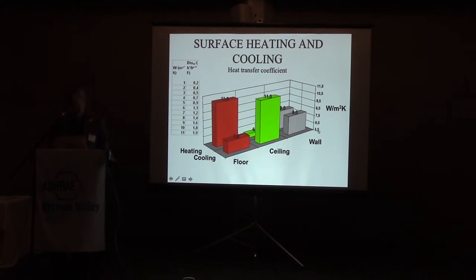So that's mainly radiation. If you have a ceiling, it's the other way around. For the ceiling, you have a high heat exchange coefficient for cooling, because the colder air will fall down, and you have a higher convective part. So you could say, for the same delta T between the surface and the room, the floor is better for heating, the ceiling is better for cooling. There are some different applications, but that rule is not always valid. I'll show them. For a wall, the heat exchange coefficient is the same if you are heating or cooling.